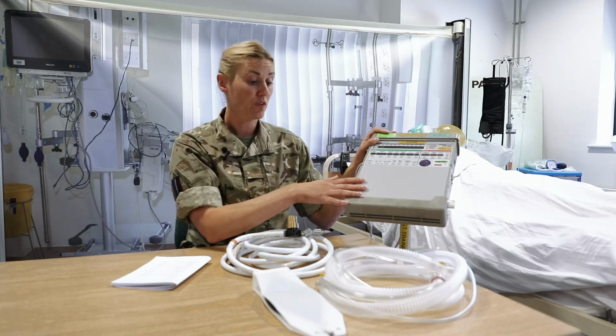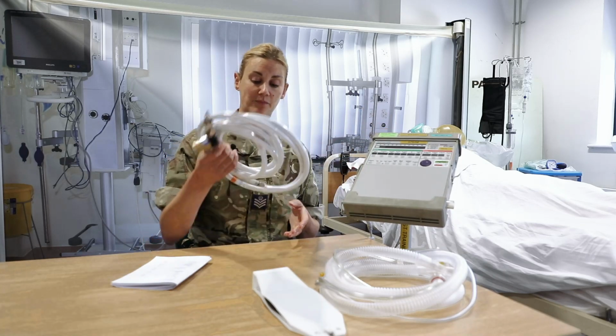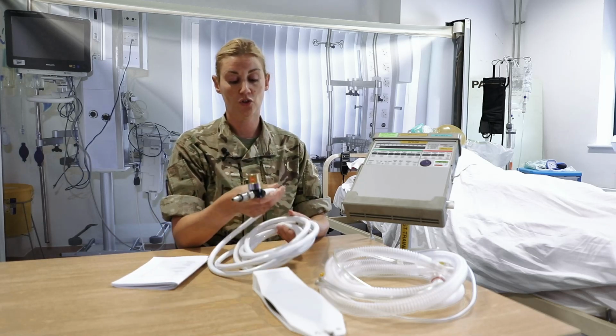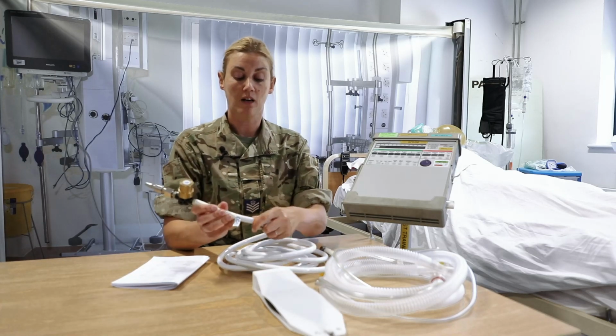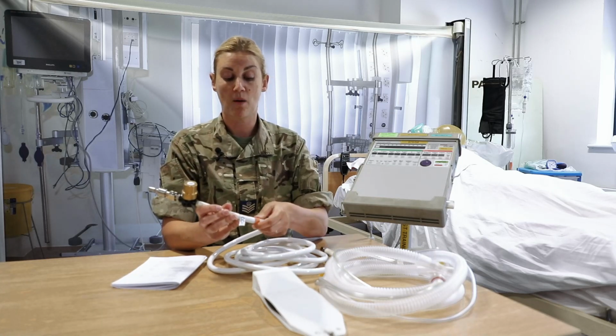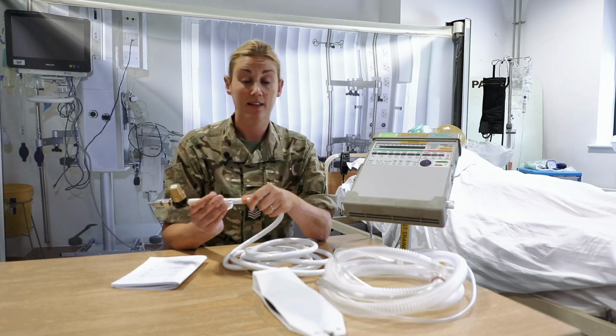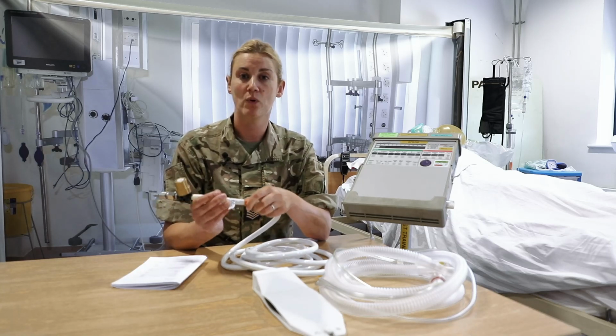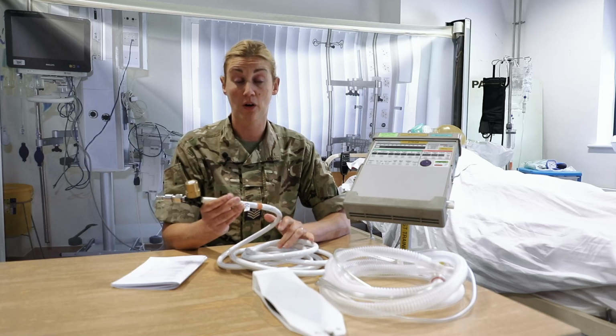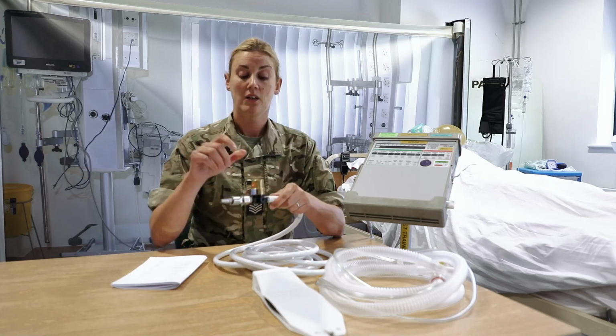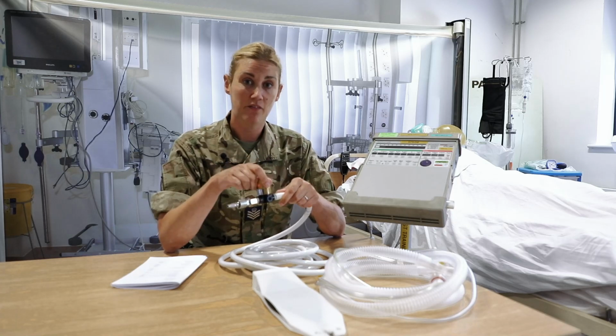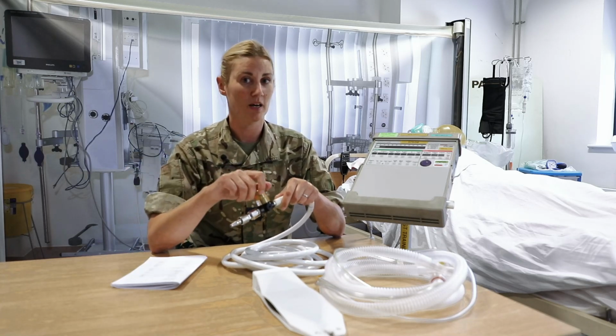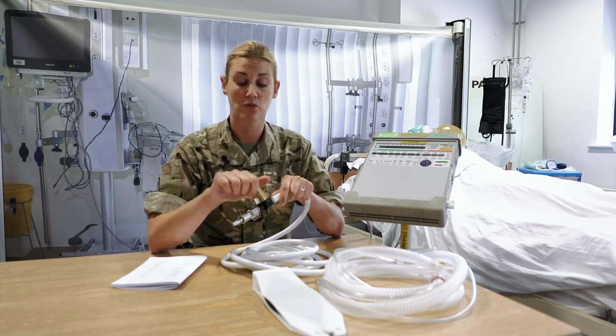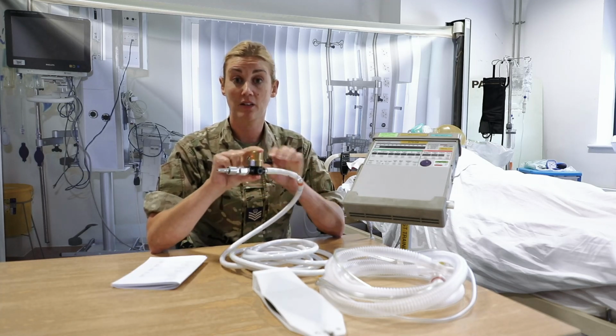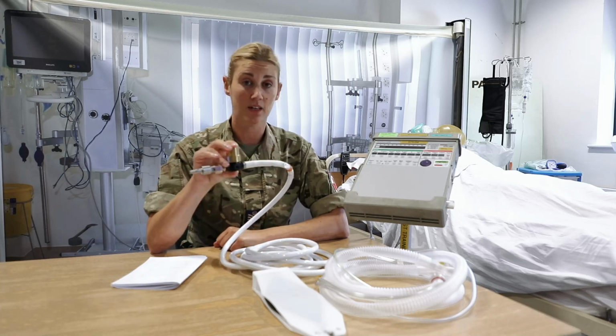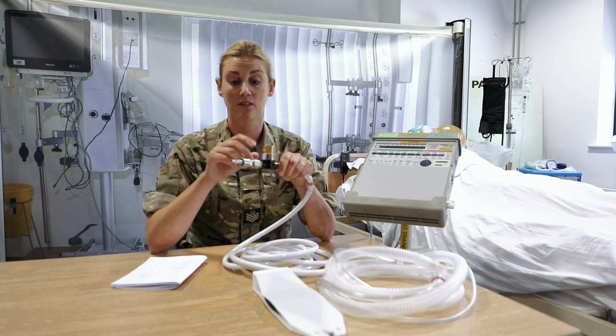Once we're happy, having given that a once over, we're going to move on to our oxygen hosing. The hosing itself should have a rubber band on it, which has got a date. This one's dated 2017. The hoses have a 4-year life, so just confirm that the hose is still in date and good to go. You should have a valve, so this is a hand tight valve. We don't want you to undo it and do it back up again. Okay, there's no need, just check that it isn't loose at all and is just hand tight. This is the one that's going to make sure it regulates the pressure sufficiently for the LTV from the cylinders.